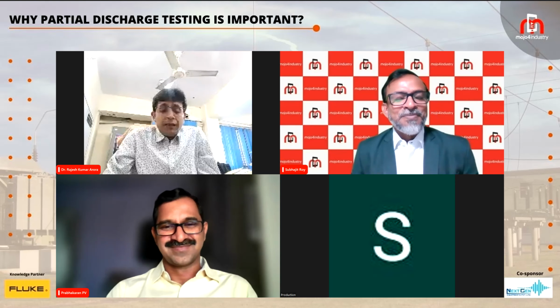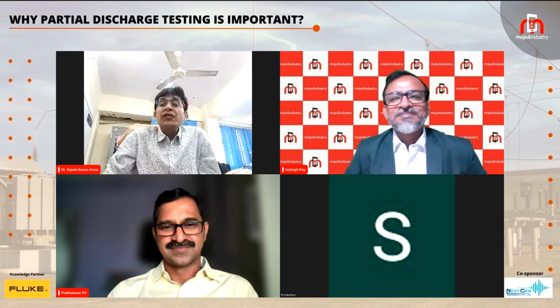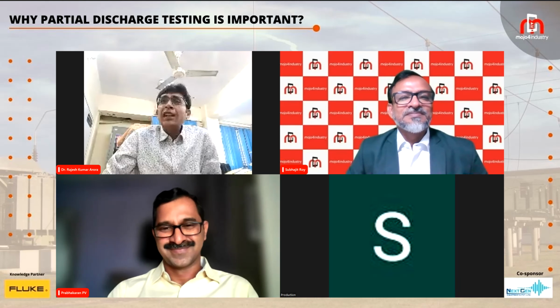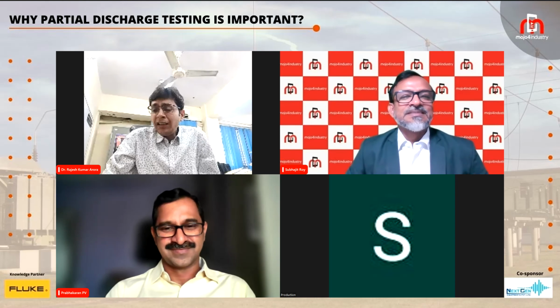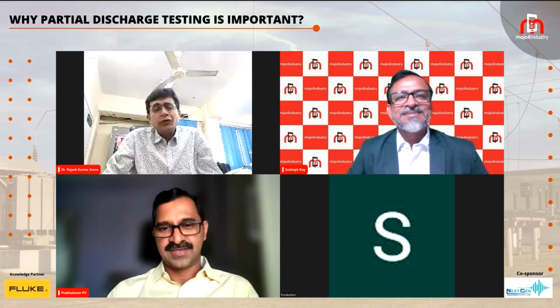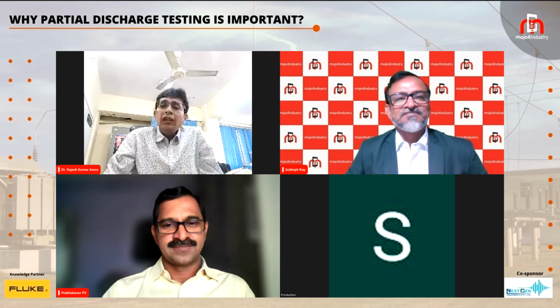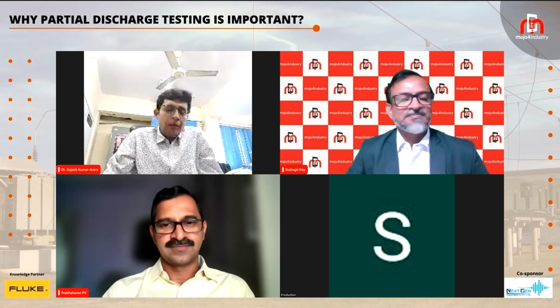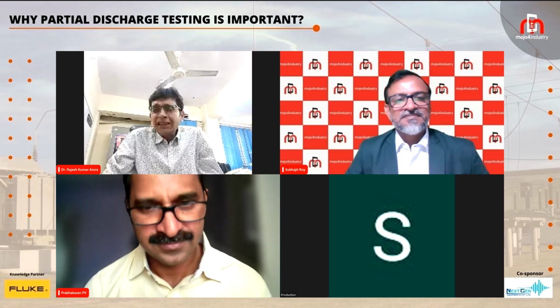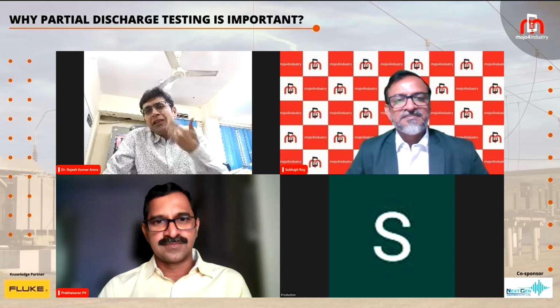Yes, I already mentioned that partial discharge is present even in the LV system. If you avoid addressing it, in the beginning it may have very little effect, but finally it leads to a catastrophic breakdown. You can't afford to avoid it in the present scenario, because availability of assets is very important to run your network, and everything is availability based. Your tariff is also decided based on the availability you provide to customers, and you can't afford any kind of breakdown in the present era.